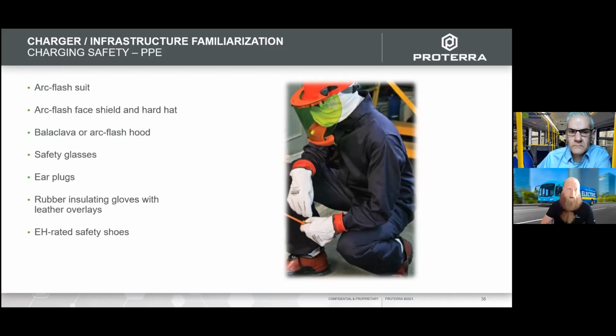Starting off with the required PPE, you're going to need an arc flash suit properly rated for the charger at hand. You're going to need an arc flash face shield and a hard hat or a hood, depending on the level of charger that you're working on. A balaclava and arc flash hood are also required, again depending on what you're working on. A balaclava, for those unfamiliar, is the white hood that the technician shown here is wearing.